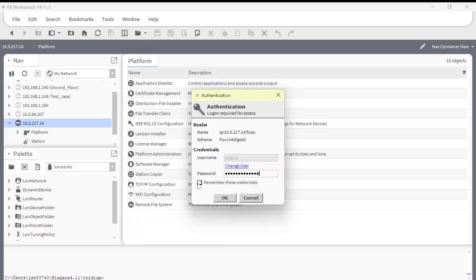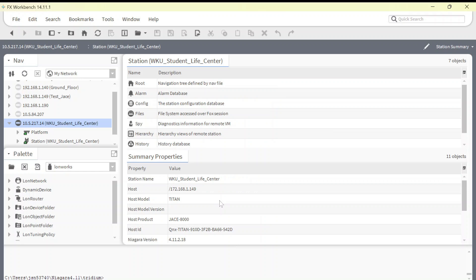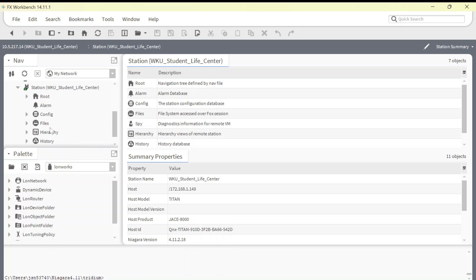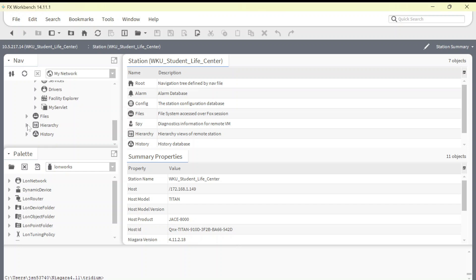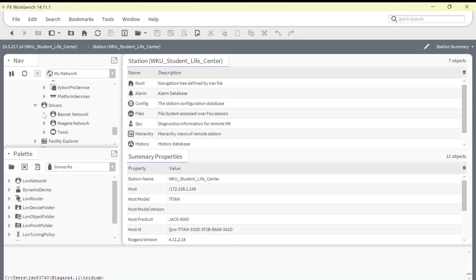Let's start with the basics of what you need to do to get those points into your system — we begin by going into Workbench. We begin the process by logging into our station in the Jace. If you're going to be adding a Jace to your Metasys server, you're going to be going through a network engine — either the NAE or the SNE — that's the only way you can pass the data directly through to the ADX server.